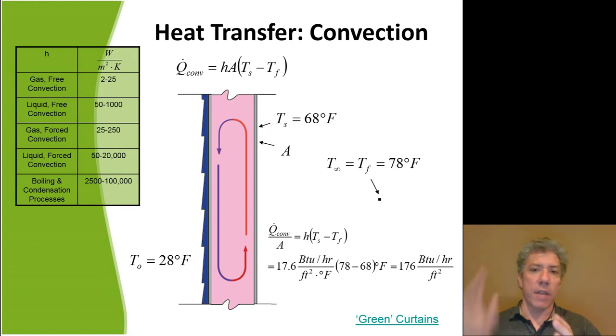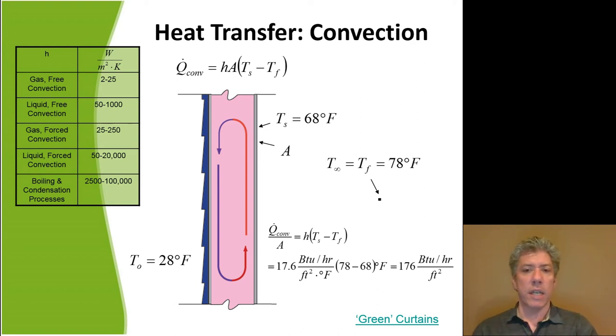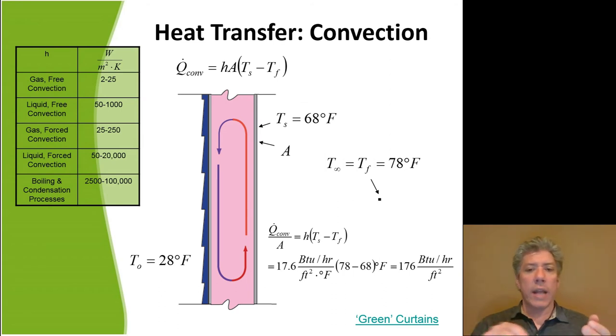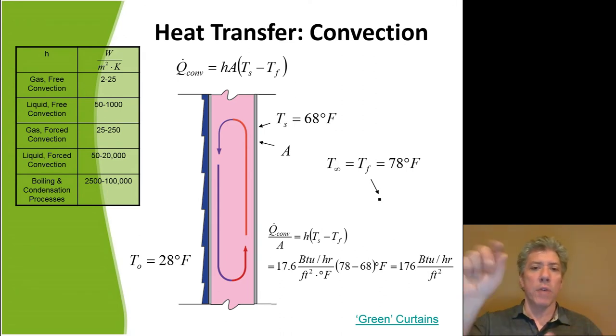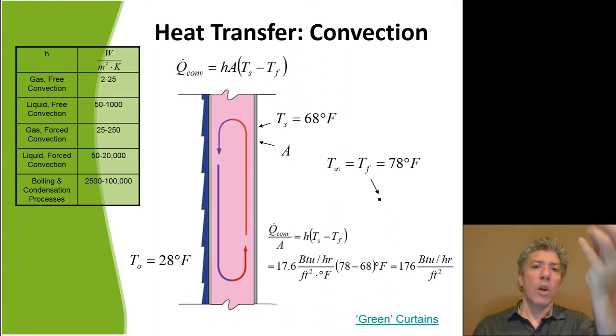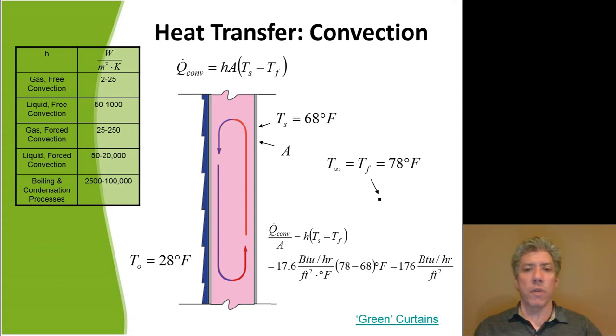If you imagine an old farmhouse wall without insulation in cross section: in wintertime with cold outside and warm inside, the air within the wall will rise on the warm inside wall side since it becomes buoyant, moves up to the top, shifts toward the outside wall, cools, and falls. This loop sets up a convective loop that actually enhances heat transfer through the wall — a bad thing. You want to resist it, which is why we use insulation.